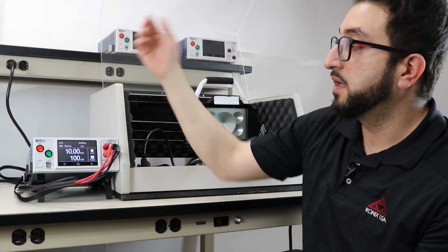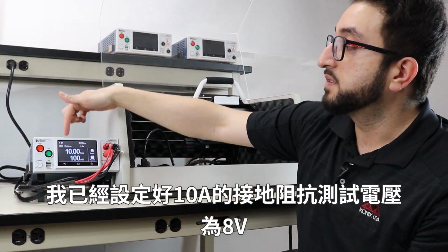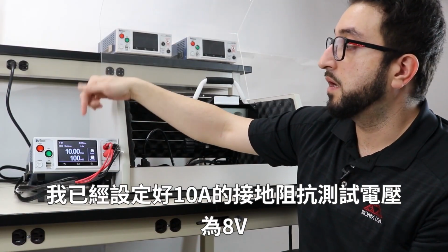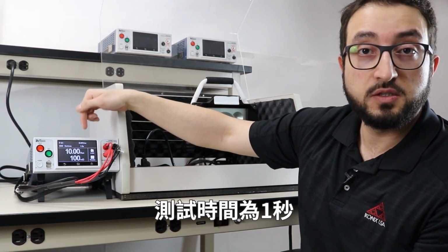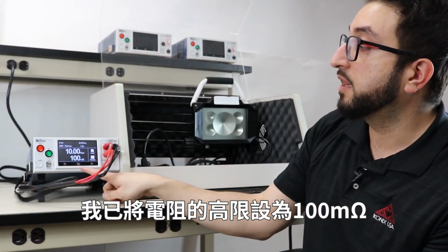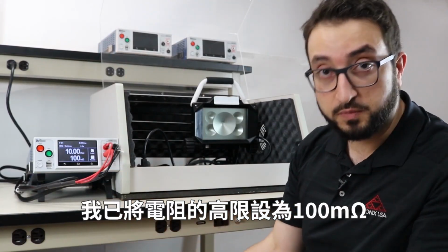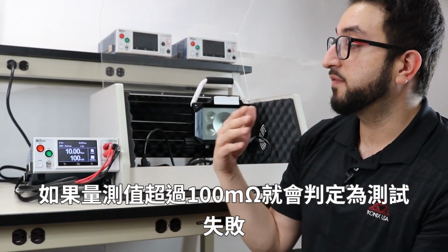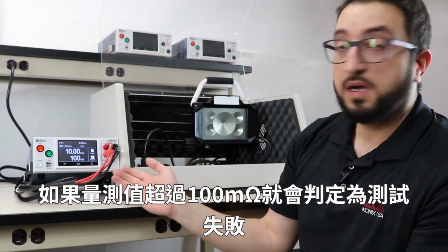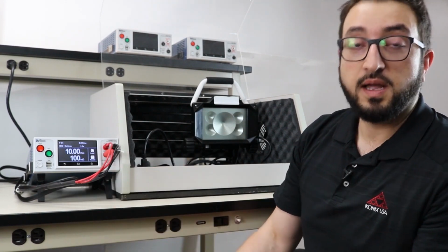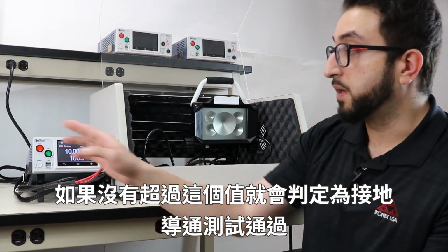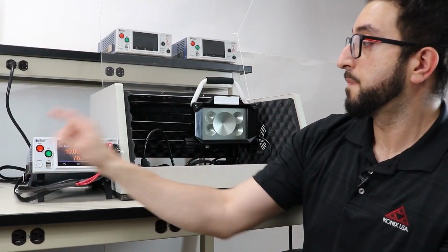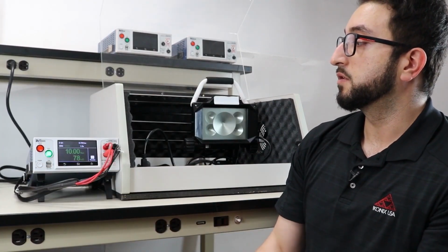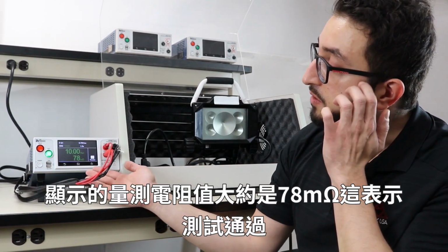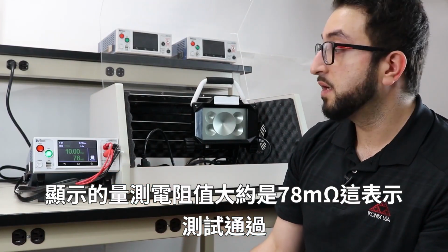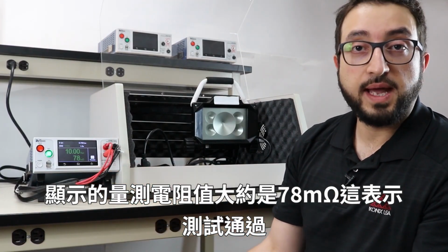On the tester side, I've programmed a 10 amp ground bond test at 8 volts and 1 second dwell time. And I've set my high limit for the resistance to be 100 milliohms. So now when I run the test, if the measurement exceeds the 100 milliohms, this should result in a failure. And if it doesn't, then we will have a pass ground bond test. So as you can see on the screen, the resistance measured was about 78 milliohms, and that indicates a pass.